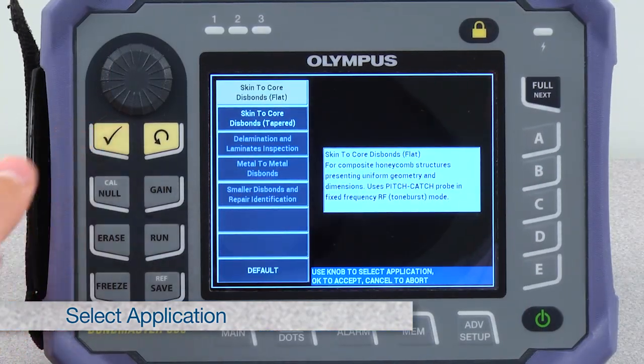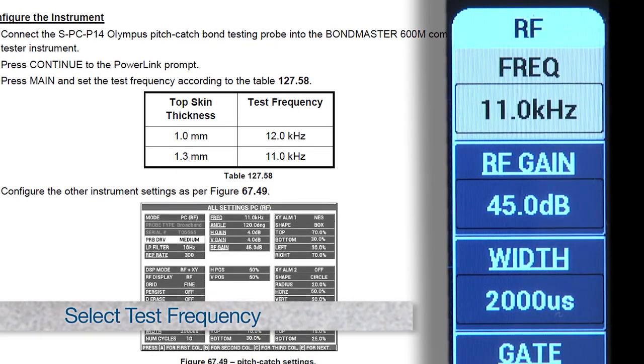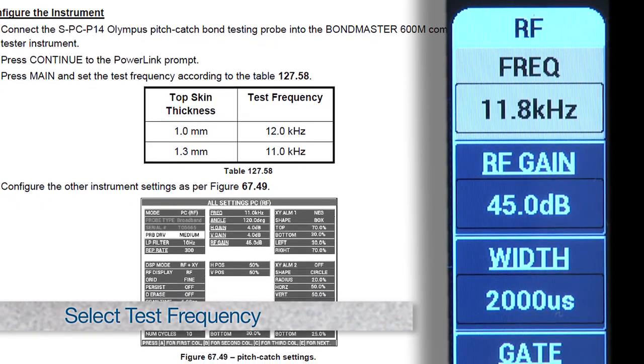Select the first application that is named skin-to-core disbonds flat. Select the proper test frequency as recommended by either the original part manufacturer or the inspection procedure.